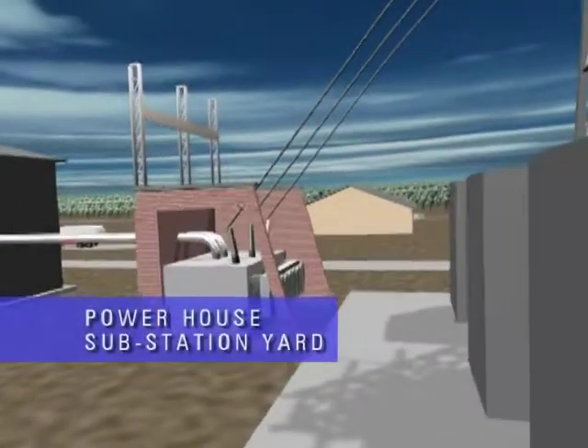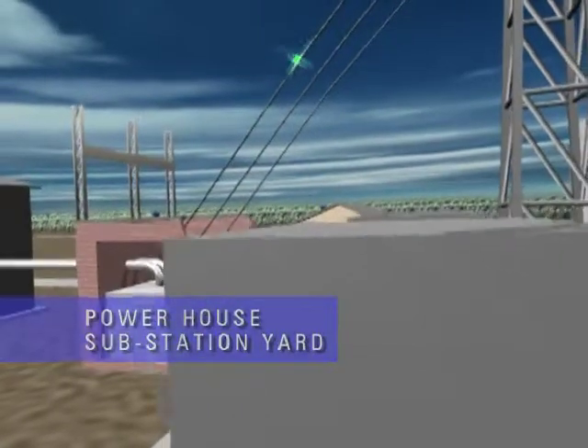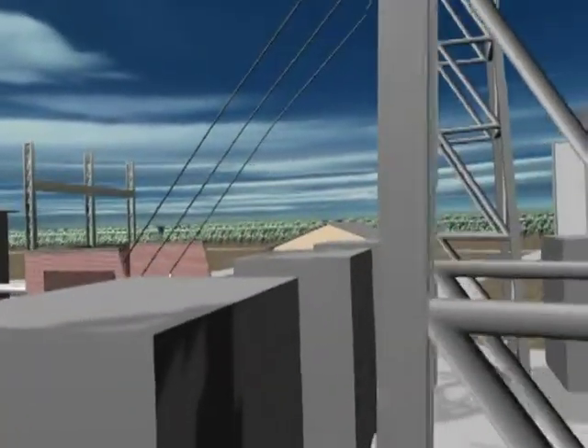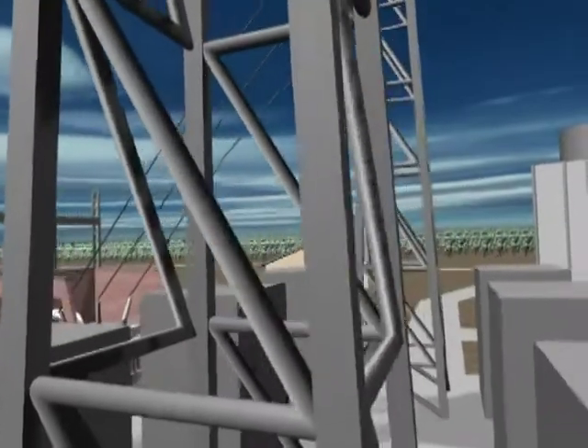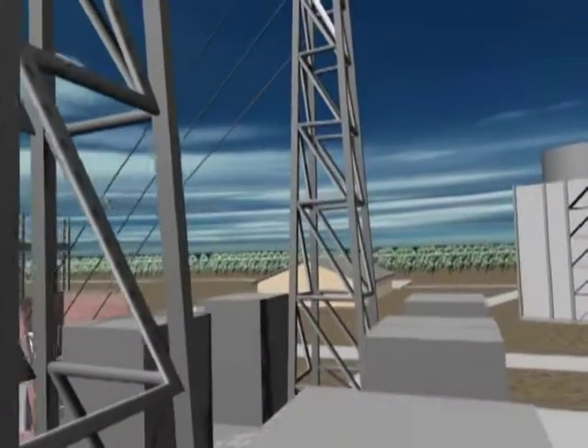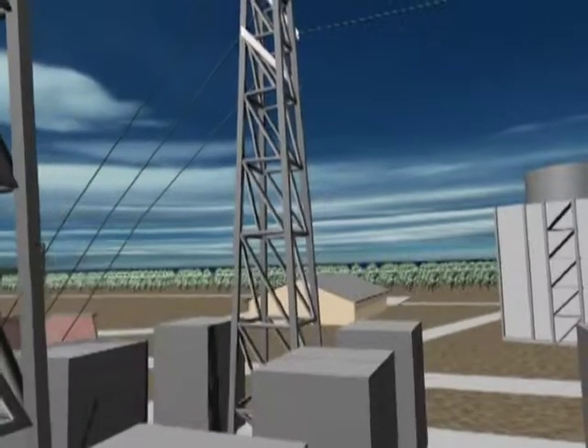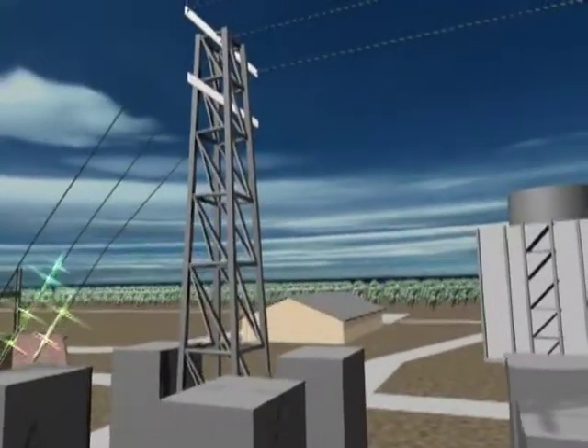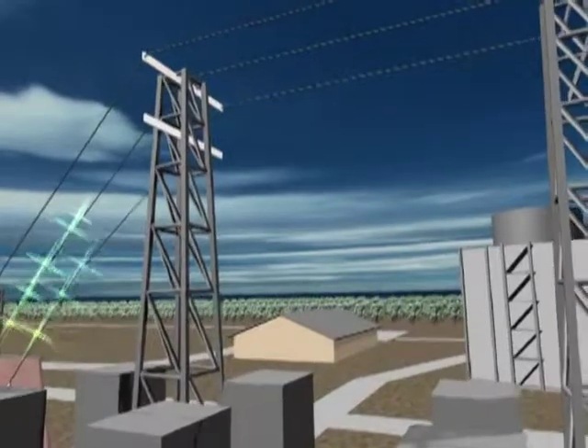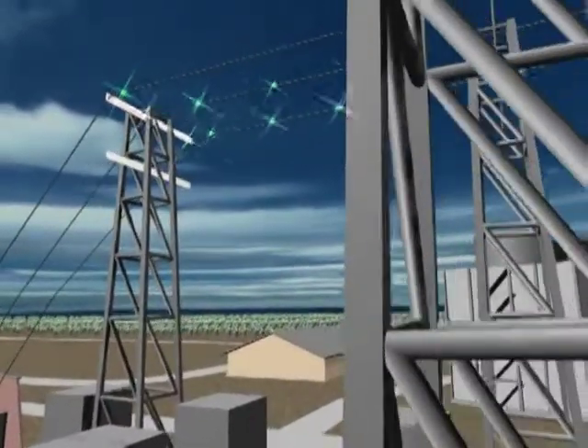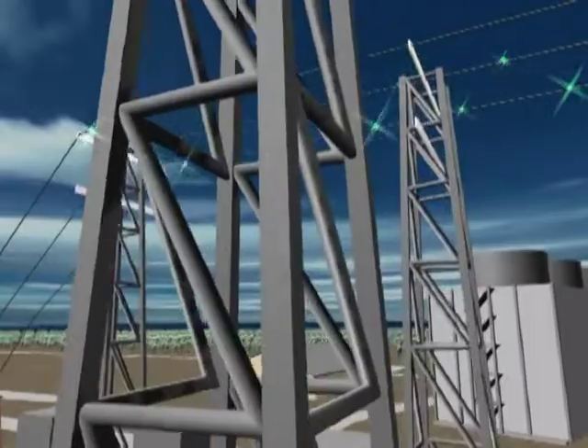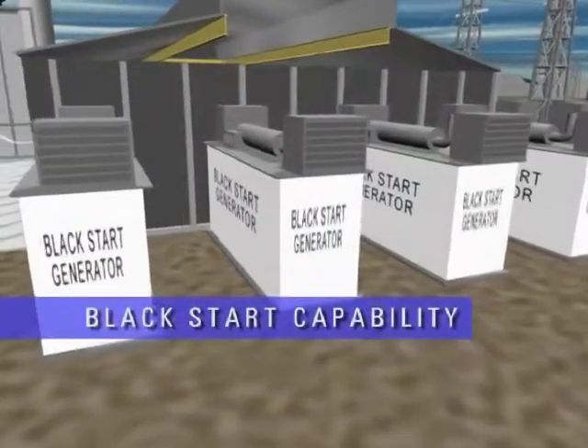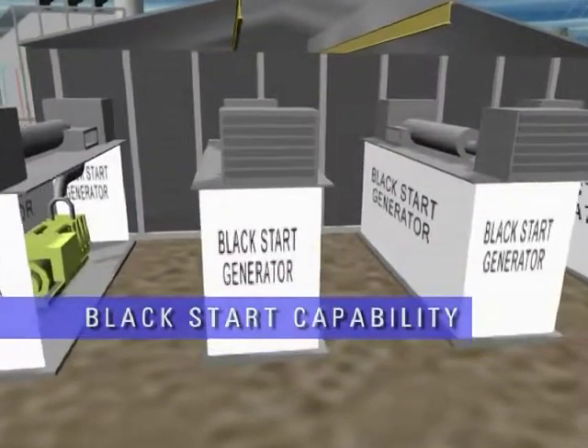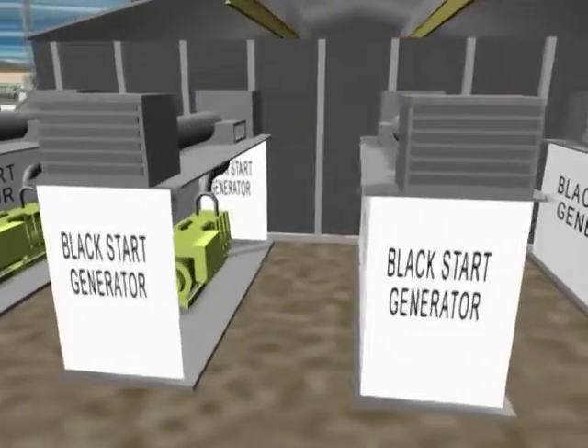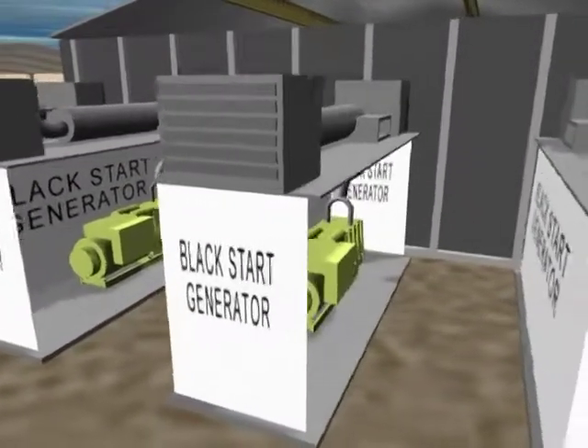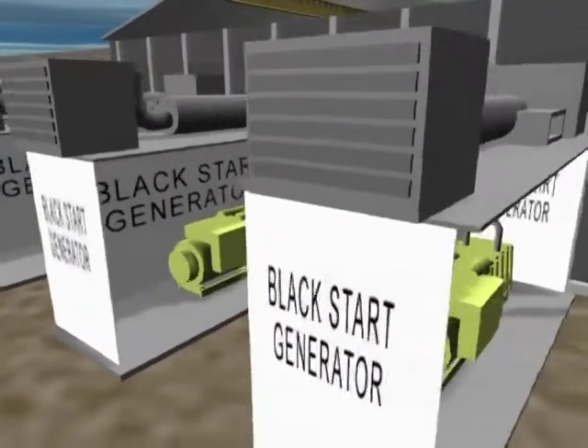The powerhouse and substation yard contains all generation and utility interconnect components consisting of dedicated steam turbine generator sets, which include control systems, cooling systems, circuit breakers, utility paralleling switchgear, generator step-up transformers, and electrical substation and towers, where the electricity generated is distributed to the utility grid. Should black start capability ever be necessary, 4 2-megawatt diesel engine standby generator sets are located next to the power island in the event of a central utility company failure.